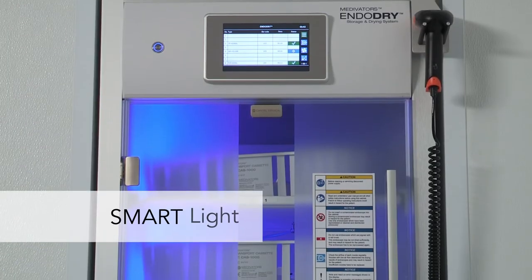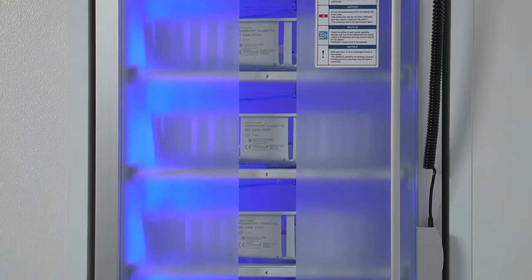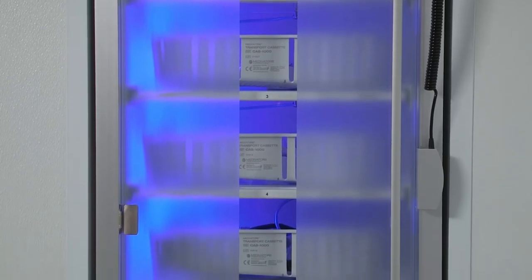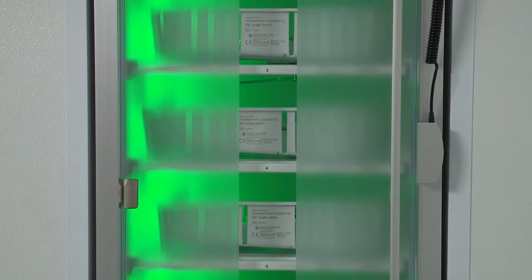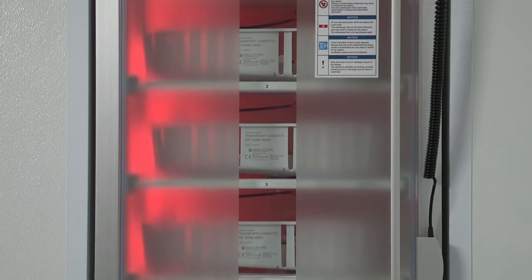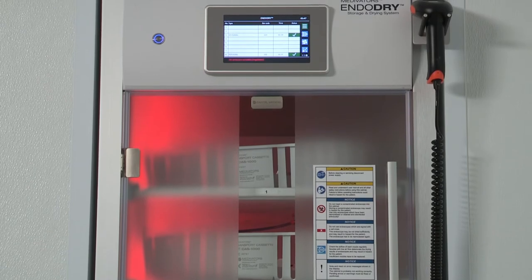The Smart Light feature with blue, green, red, and white light indicators allows for quick cabinet status identification. When the overall color is blue, at least one endoscope in the cabinet has not reached the drying time for the internal channels, or there are no endoscopes in the cabinet. When the overall color is red, the cabinet may have experienced a power failure, pressure malfunction, or at least one of the endoscopes in the cabinet has exceeded the maximum storage time and will need to be reprocessed prior to patient use.